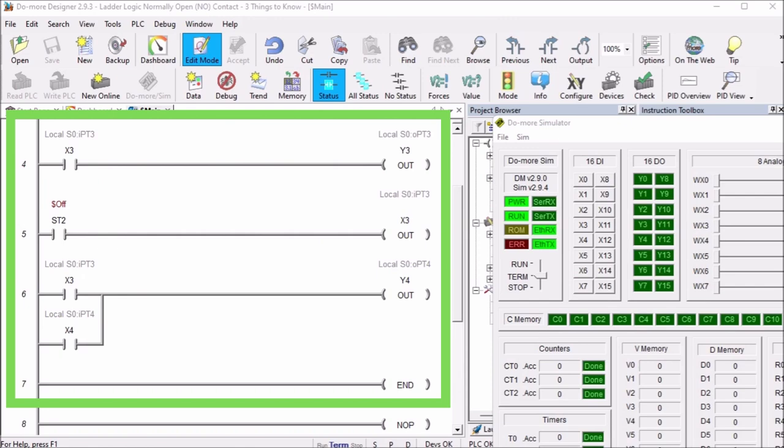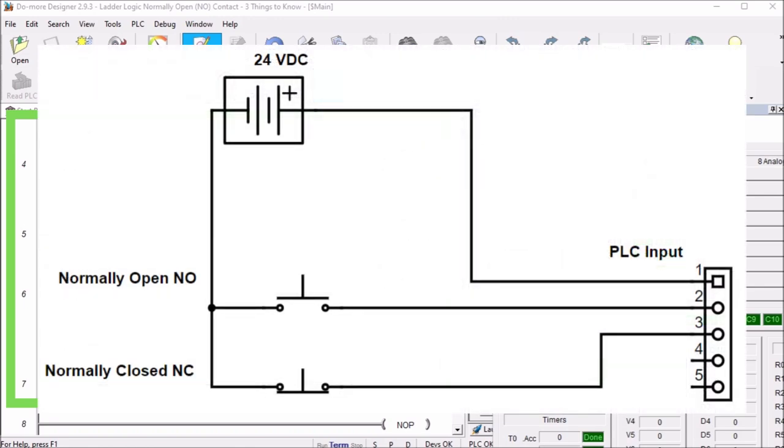Now the third thing about normally open contacts is they're not the same as wired inputs. Let's just take a look at our wiring diagram here. You'll notice that we have our power supply and we're feeding plus voltage into the PLC input on the common of our input card. Then we have a normally open push button which fed into the first input, and a normally closed fed into the second input of the PLC. What we can do is actually look at that PLC.